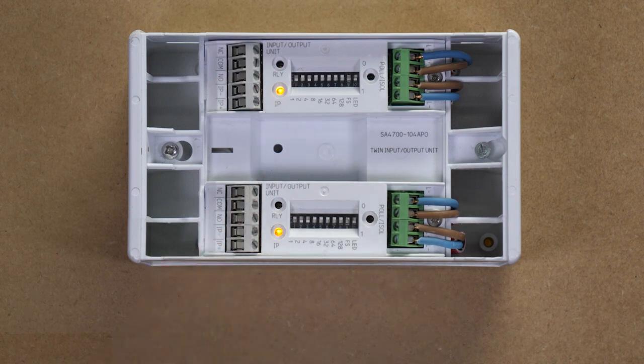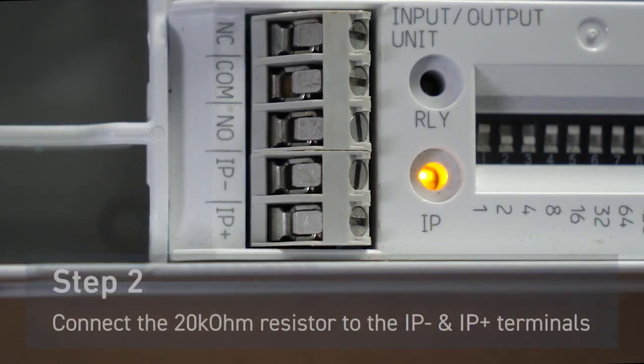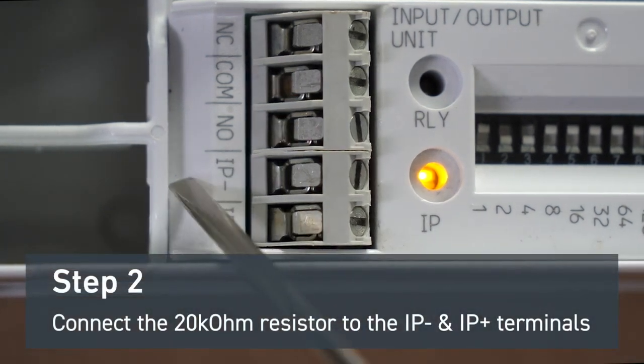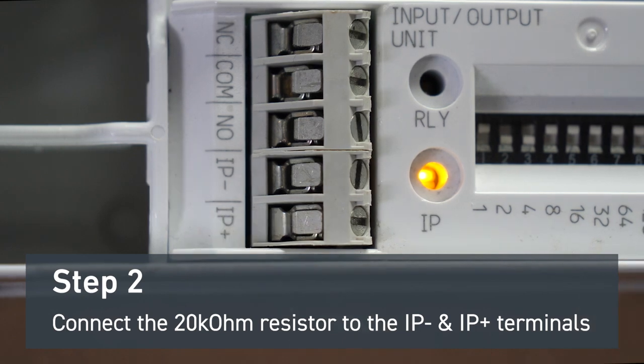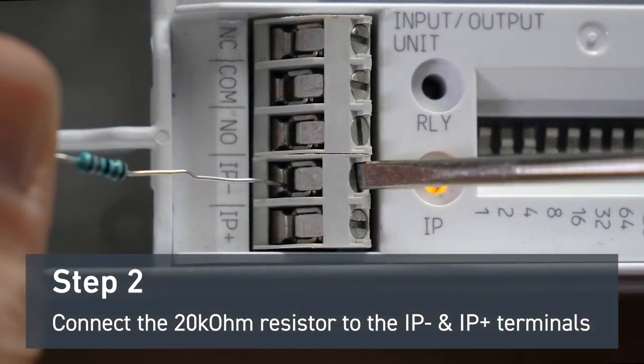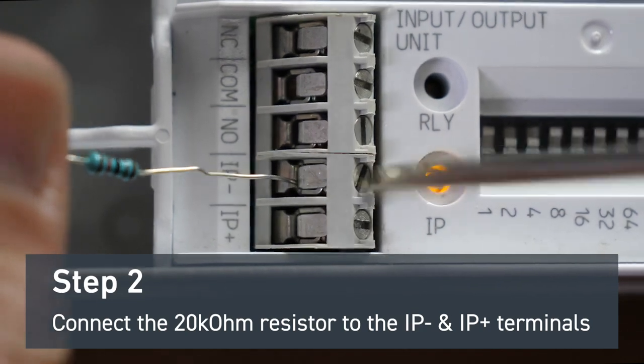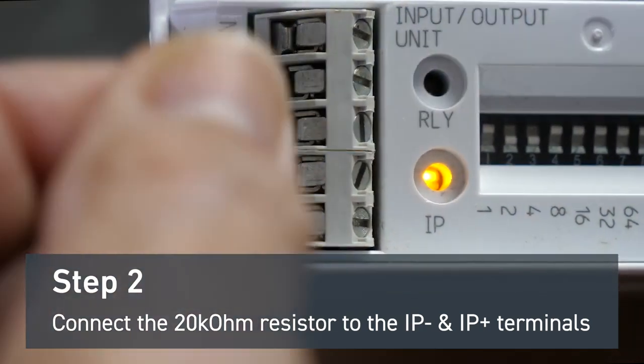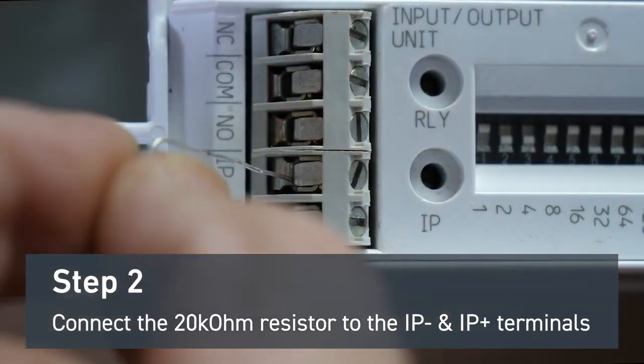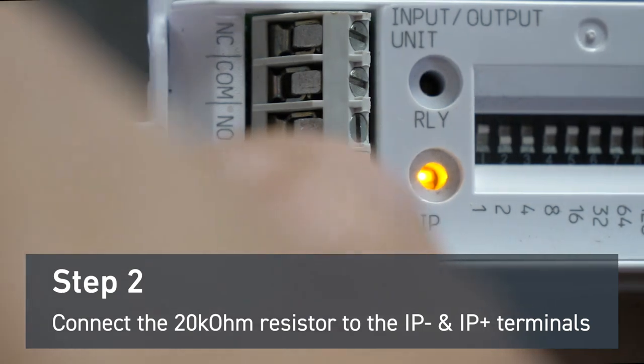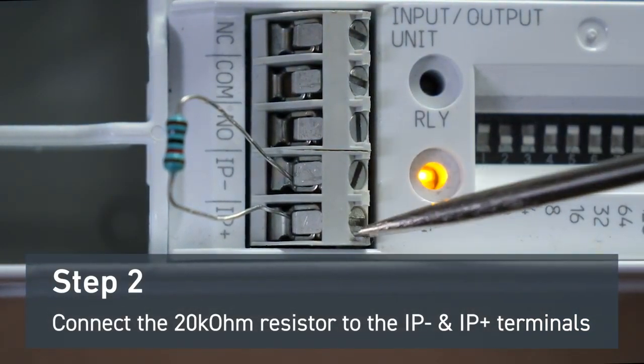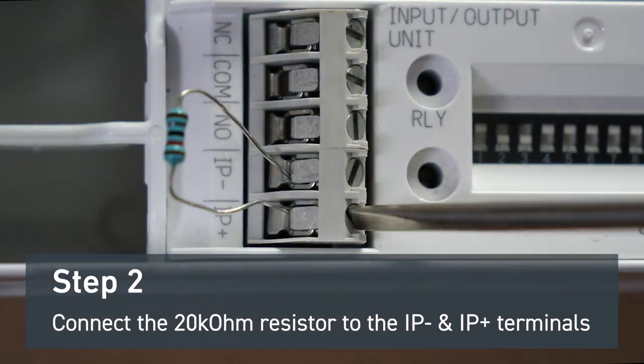If you're not using the input then it will be required to fit a 20k ohm resistor which we supply into the IP negative and IP positive connections of the unit. Once this is connected you will notice the yellow input fault light extinguish.